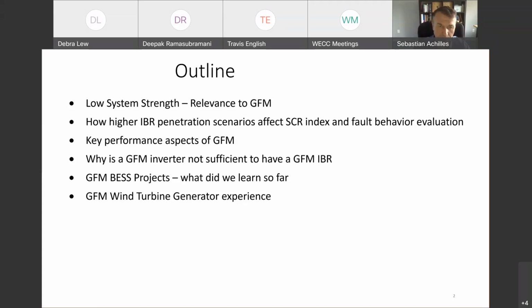The next bullet is related to why grid forming inverters are not sufficient to have a grid forming inverter-based resource. Sometimes we get caught in this idea that grid forming behaves like a voltage source, or that grid forming inverters are the only thing that matters. Not intentionally, but as manufacturers we start worrying about other aspects that go beyond the inverter. This may help address questions about whether you can simply change the inverter code and go from grid following to grid forming, and in what cases that's actually not sufficient. That would be the idea of that slide.